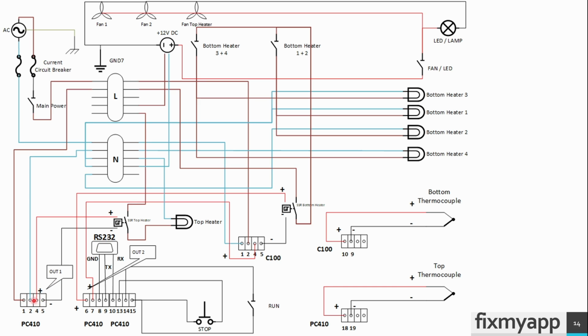When the program starts for this temperature controller, it will drive this solid state relay and it will switch this circuit on. So this circuit will provide power to the top heater. Terminal 4 and 5 is known as output 1. Terminal 8, 9 and 10 is used for the serial communication. Terminal 8 is ground, terminal 9 is a transmit line, and terminal 10 is the receive line.